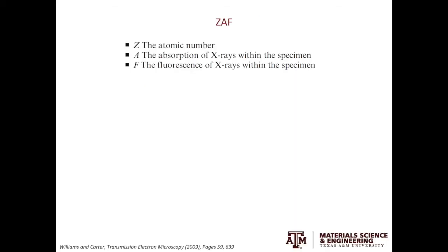Moving forward, when doing EDS quantification, there are three things we need to consider. It's called ZAF. Z represents the atomic number. A is the absorption of X-rays. F is the fluorescence of X-rays.